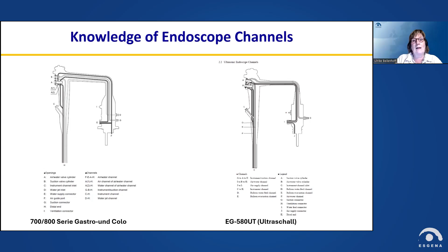So if I have a look at the time and frequency, we have periodic intervals, and the majority of the guidelines say at the moment that each endoscope should be sampled at least once a year. And you should take into account that from each endoscope product family, different endoscopes are sampled, and that is just an example: gastroscope as product family 1, or bronchoscope as product family 3. And if you want to sample, you should not take the endoscope directly from the washer disinfector and then sample. This can be done in validation processes. But if you do a periodic sample, then you should store the endoscope for at least 12 hours to give the microorganisms a little bit of time to grow, and then you have a chance to find them.